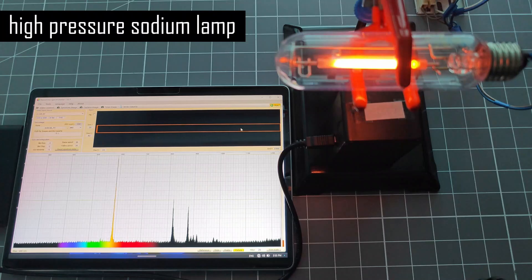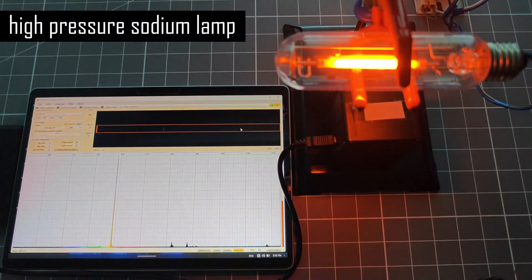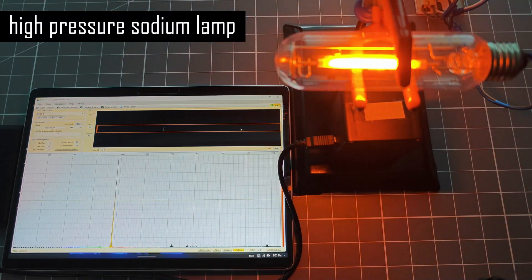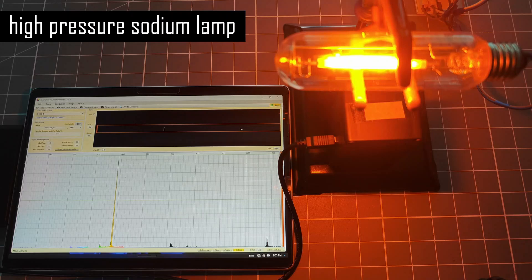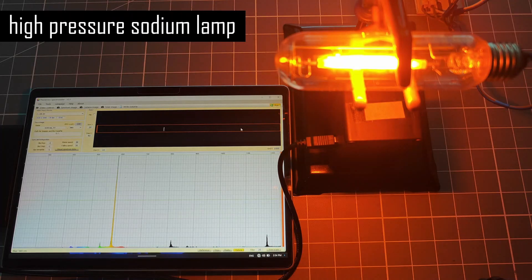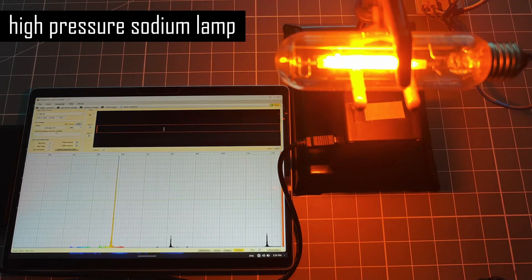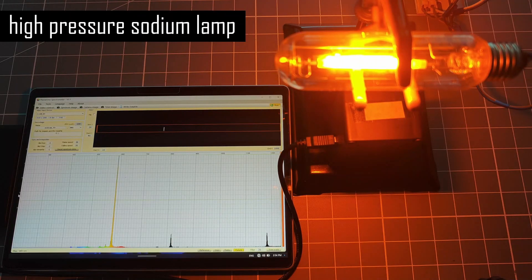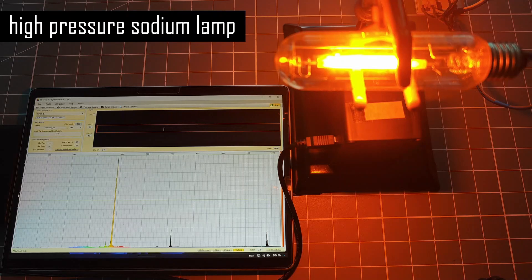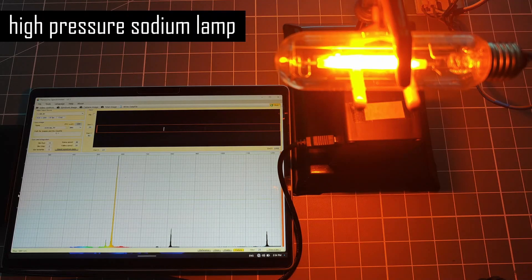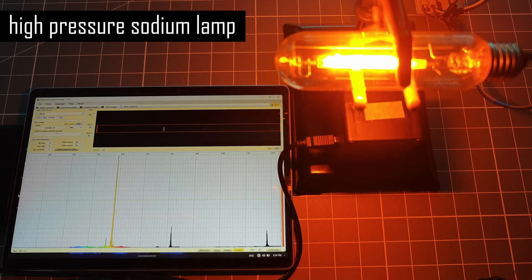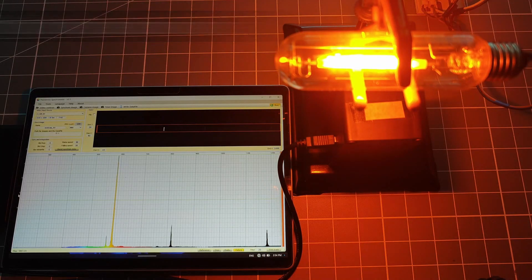And as for the spectral resolution, we found this to be around 1 nanometer. It is possible that this is even lower. Mr. Kang has collected spectra that can resolve the double peak of the main sodium lamp line. This would put its resolution closer to half a nanometer or less.